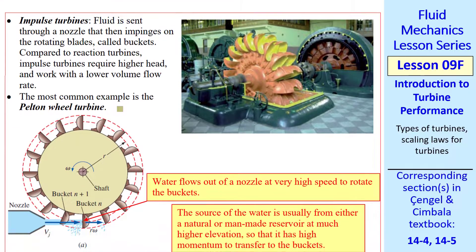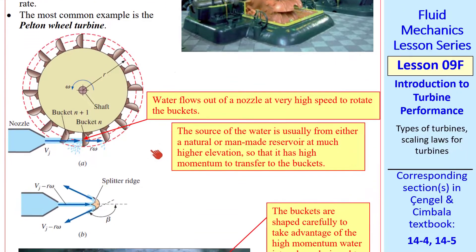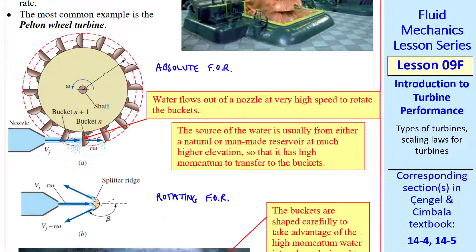Let's talk about impulse turbines first. In an impulse turbine, fluid is sent through a nozzle that impinges on the rotating buckets. Impulse turbines require high head but work with a small volume flow rate. The most common is a Pelton wheel. The water jet comes from the left and turns the wheel; the shaft is then attached to a generator. I have two schematics: the top one is in the absolute frame of reference, and the bottom one is in the rotating frame of reference rotating with the turbine. We have very high head water coming from an upper reservoir, sent through a nozzle so a jet impinges on the buckets, giving it momentum that turns the bucket.